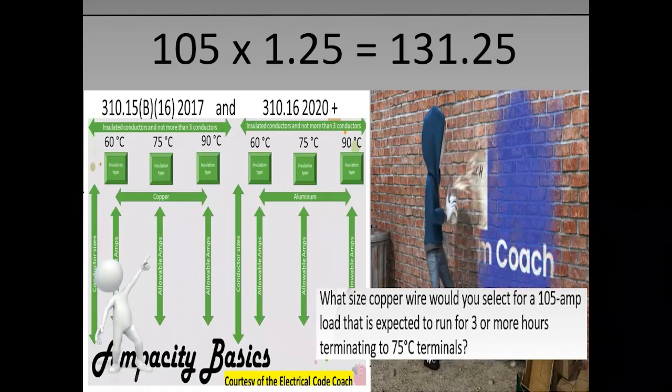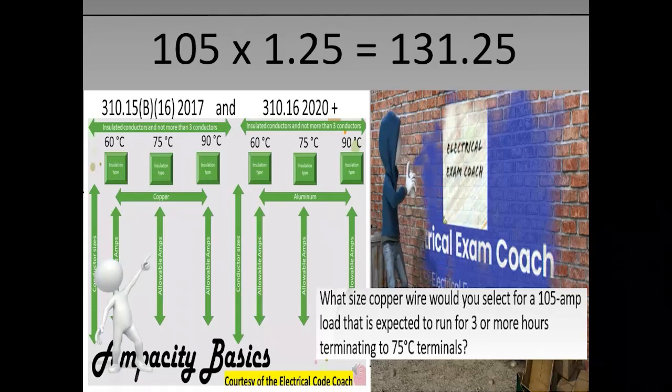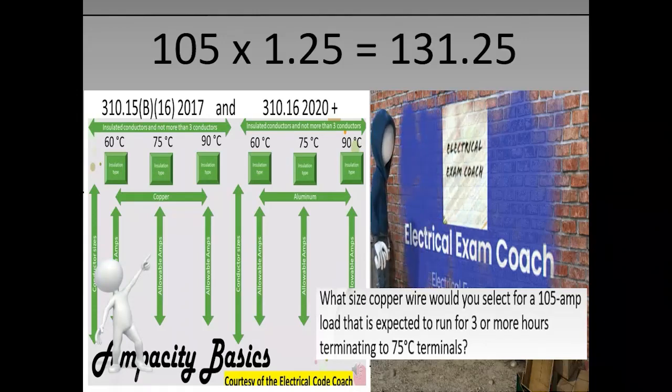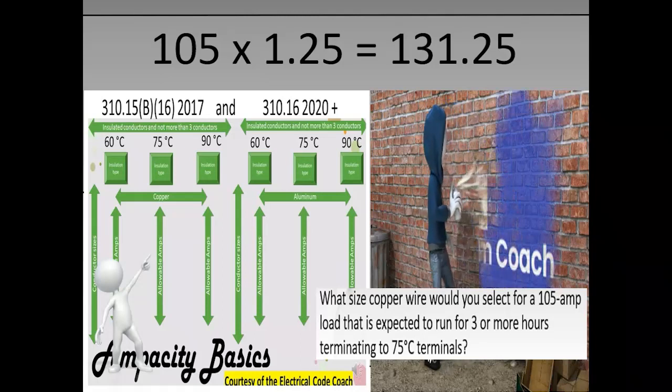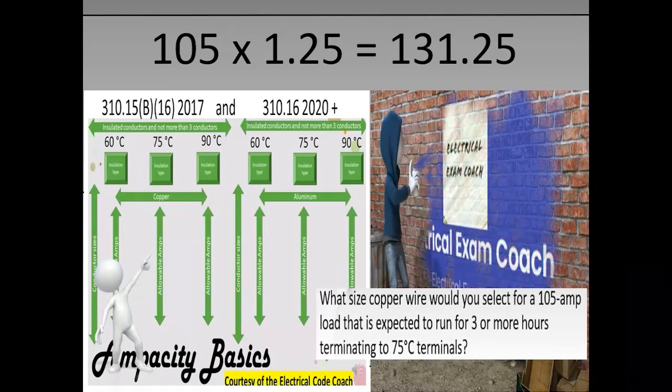We did the 125% because it's a continuous load. Then we're going to head to our primary ampacity table. We're going to choose from the 75 degrees C column in this case because it states that we're terminating to 75 degrees C terminals.